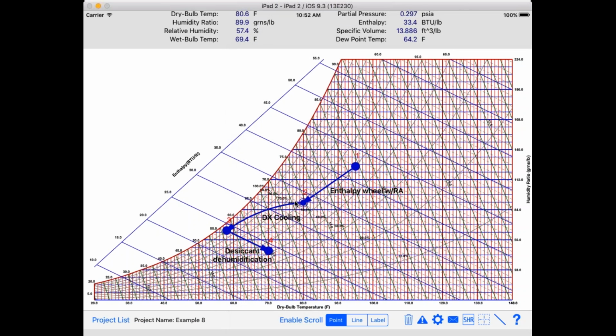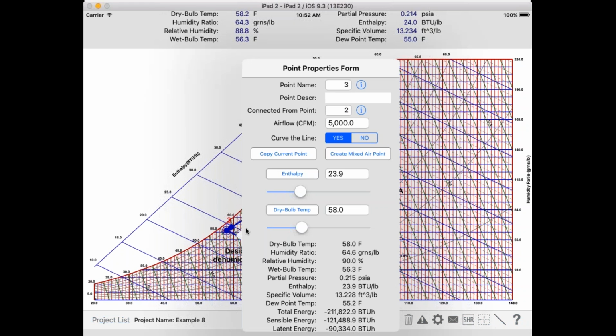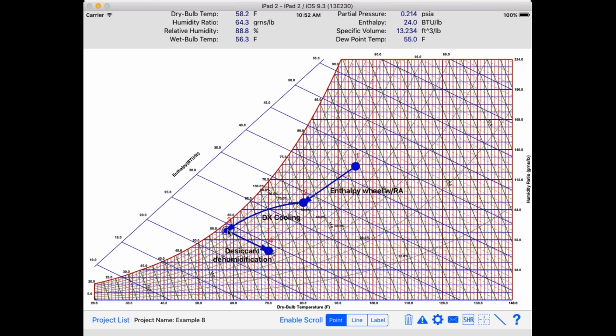Then at that point, I'm passing the air through DX mechanical cooling almost all the way to saturation, and my conditions here are 58 degrees dry bulb and 90% relative humidity. Then at that point, I'm passing the air through a desiccant dehumidifier.